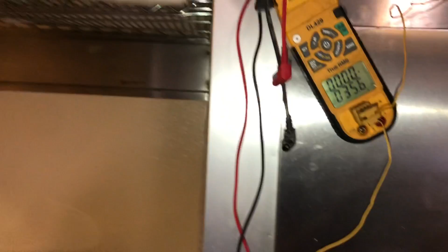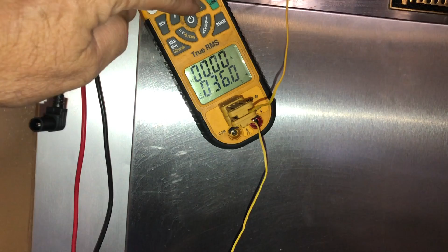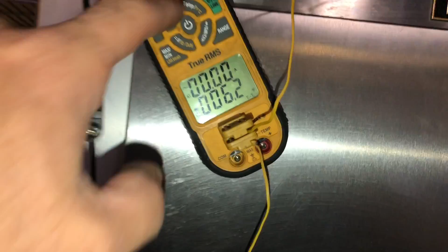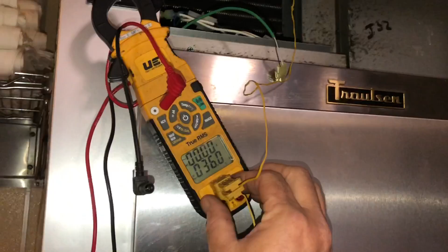Dual temps read on one line. T1 is the evaporator sensor, at 35 or 36 degrees. T2 in the cabinet down here is 42 degrees, and the difference between the two is 6 degrees. So we want to check T1, I'm at 35, let's get an ohms reading. We'll call it 36 degrees.